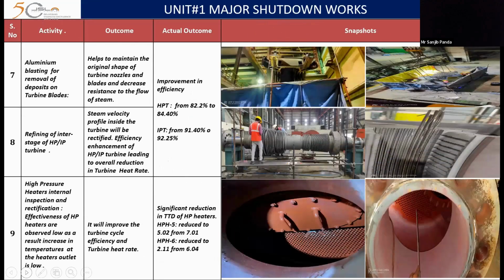Then aluminum blasting for removal of deposits from turbine blades. This is to recover the heat rate degradation in the turbine. Refining of interstage HP and IP turbine has also been done. High pressure heaters internal inspection and rectification as per the observation has been carried out. This is on the turbine side, all three of them. Next one.